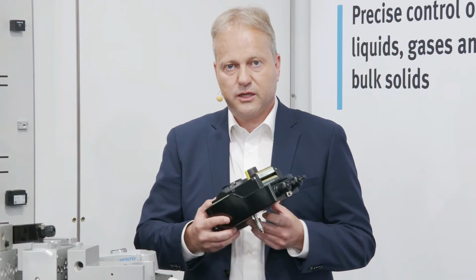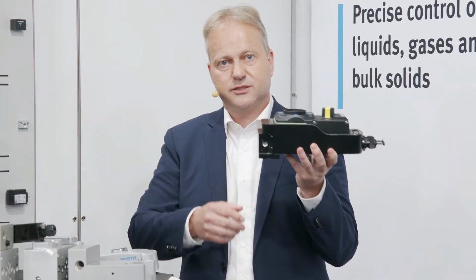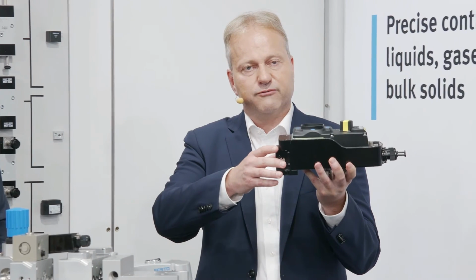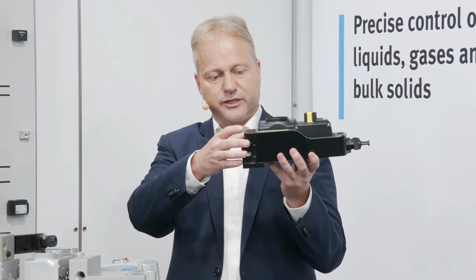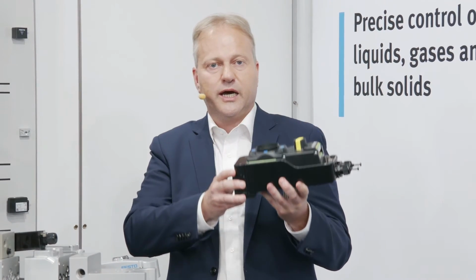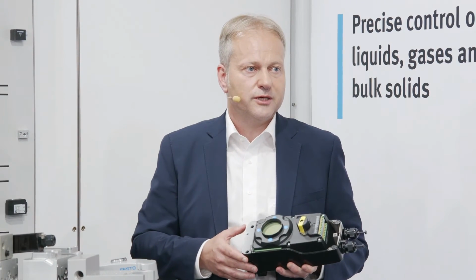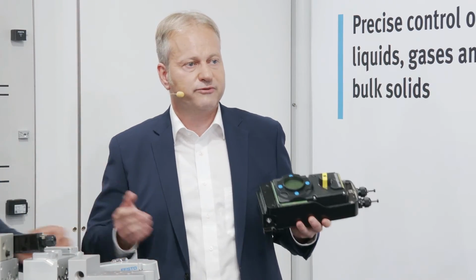We have digital outputs for status feedback, for example, as an option. And also what we have as an option, we have our mounting interface. This mounting interface is especially for our new standard here, but we have also different mounting interfaces, like the conventional one, the classical installation one. It's simply done by this pneumatic adapter here. And also we have options like a fail-in-place version, like a fail-safe version. So there are many possibilities to fulfill the requirements for different kinds of application.